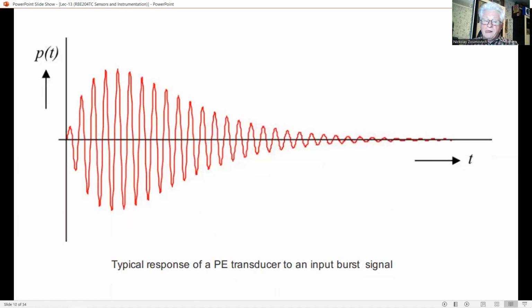Piezoelectric transducers operate best at resonance. The high stiffness of ceramic material results in a narrow bandwidth, in other words, a high mechanical Q factor. The resonance frequency is determined by the dimensions of the crystal, and to a lesser extent by the matching element. Popular frequencies are 40 and 200 kHz. Many acoustic detection systems use tone burst signals.